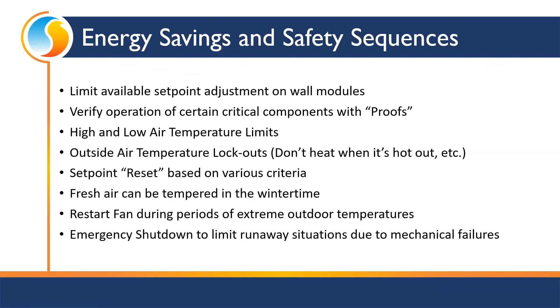One very nice thing with Prolon is that when we're dealing with other sensors, it doesn't matter, duct temperature, duct pressure, CO2, humidity, any of these other sensors, we use industry standard signals. So you do not have to special order in the Prolon specific sensor because that's the only one that will work with the Prolon system. You can go get anybody's sensor and put it on, as long as it meets the universal signal criteria that we have, which, you know, temperature is going to be a 10K type 3, or duct pressure is going to be a 0 to 5 or a 1 to 5 volt DC signal. These are industry standards. You can find these sensors everywhere.